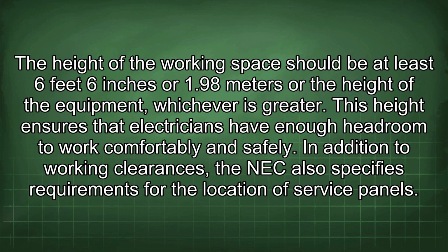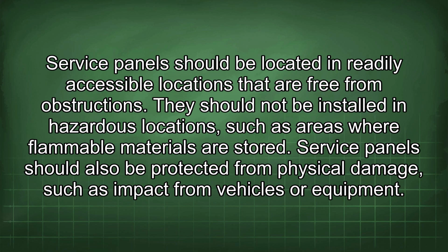In addition to working clearances, the NEC also specifies requirements for the location of service panels. Service panels should be located in readily accessible locations that are free from obstructions. They should not be installed in hazardous locations, such as areas where flammable materials are stored. Service panels should also be protected from physical damage, such as impact from vehicles or equipment.